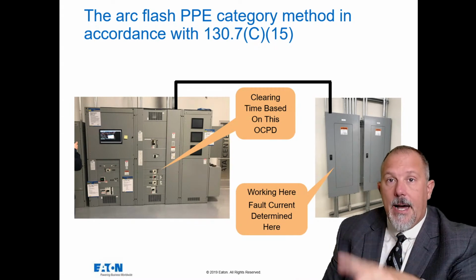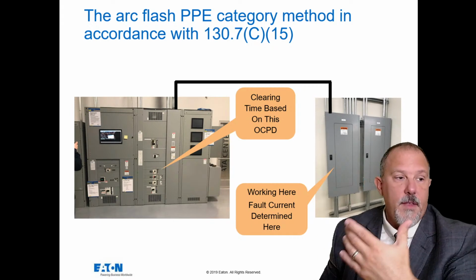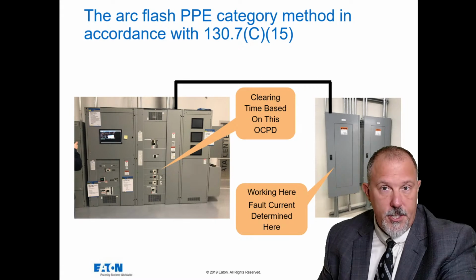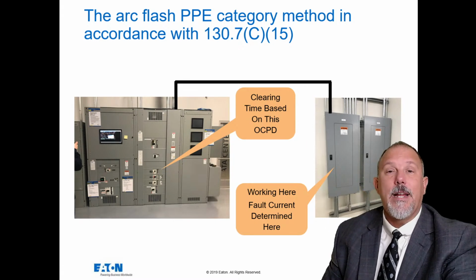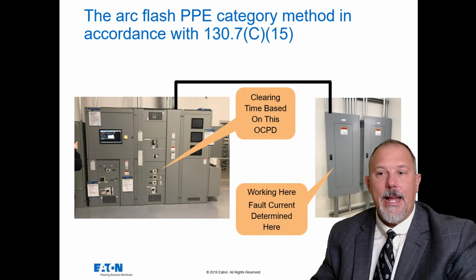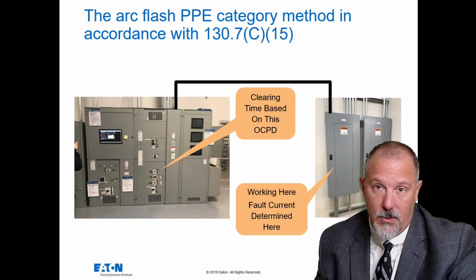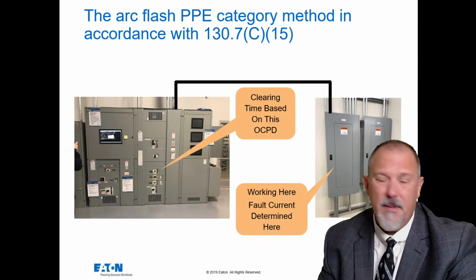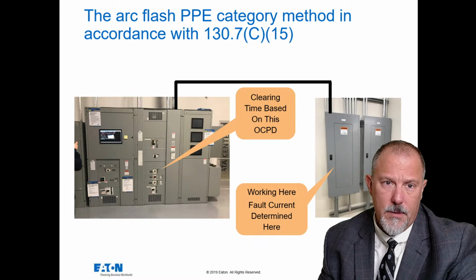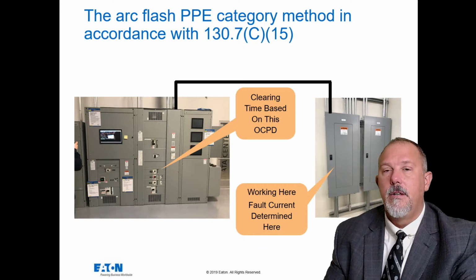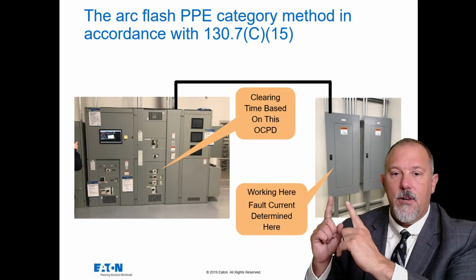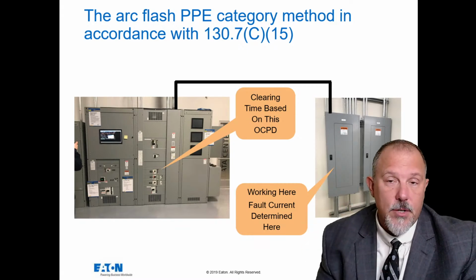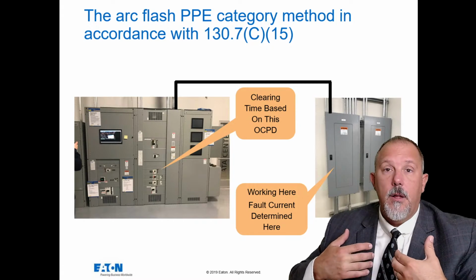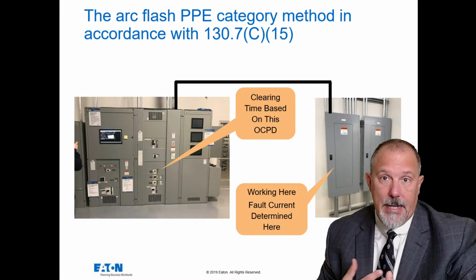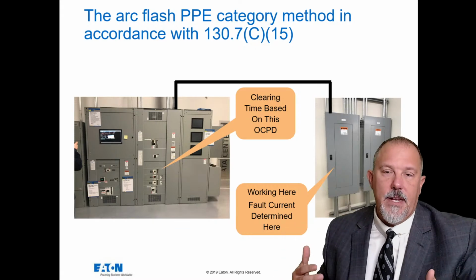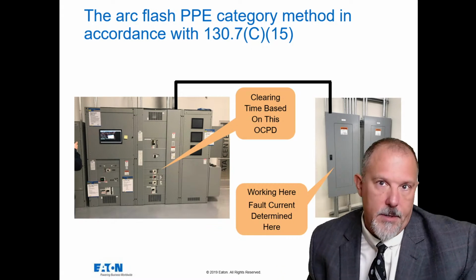Circuit breaker upstream, I can equip that circuit breaker with an arc reduction maintenance switch such that when I turn it on, it doesn't have a 30 cycle delay. It trips in less than a cycle, or maybe 2 cycles, or faster than 1 cycle. I can reduce the amount of energy at this panel when I'm in there doing my measurements. What does that translate into? That translates into lower personal protective equipment ratings. So maybe I'm not into a 40 cal outfit. I'm into, I don't know, 4 calories of an outfit.